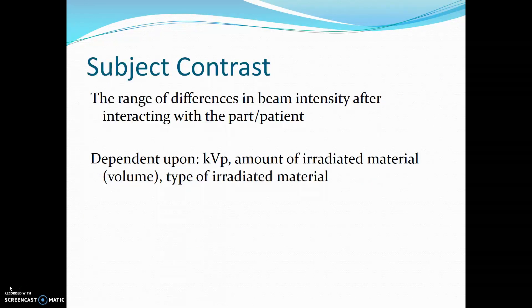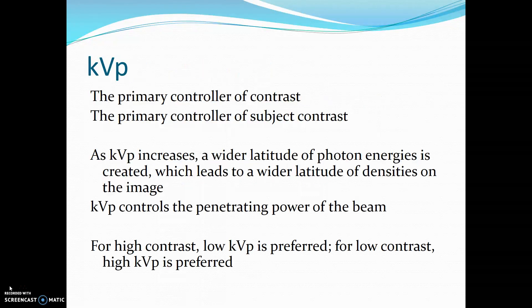Subject contrast is the range of differences in beam intensity after interacting with a part or patient. It is dependent upon KVP, the amount of irradiated material, and the type of irradiated material. KVP is the primary control of contrast and subject contrast.